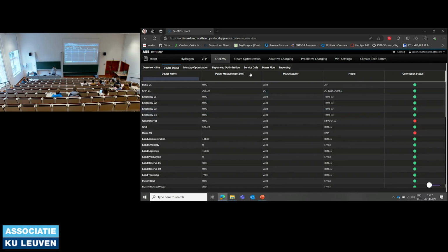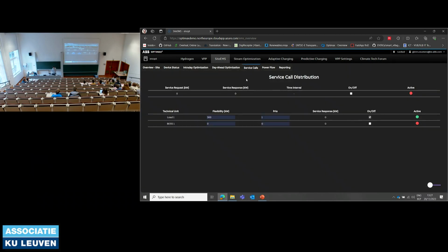What's also still being done in those real-time loops is if you have any service or grid service contracts. Here in Belgium, you can have that with Elia, for example. In the upcoming, also with the DSO now, with Fluvius, in the near future you will be able to do this. But there it's like the primary, secondary, and tertiary reserve markets, so frequency containment reserve, FCR, automated frequency restoration reserve, and manual frequency restoration reserve. So maybe if you also heard about those.